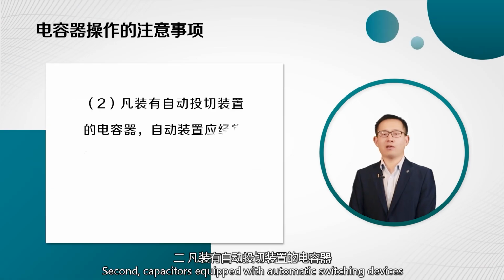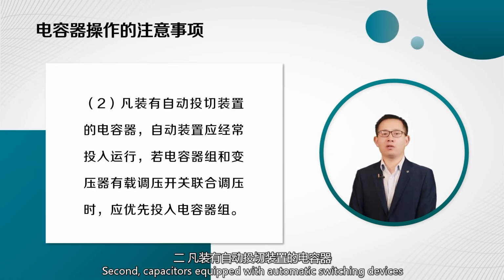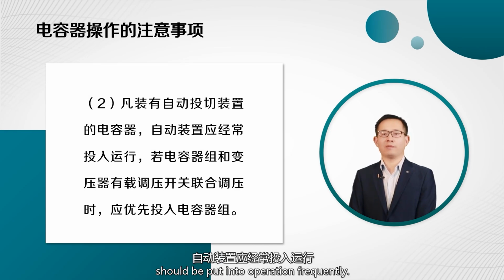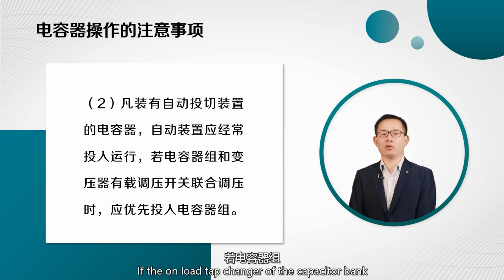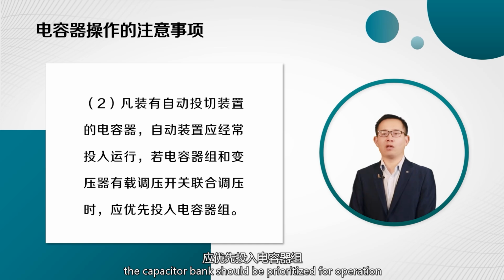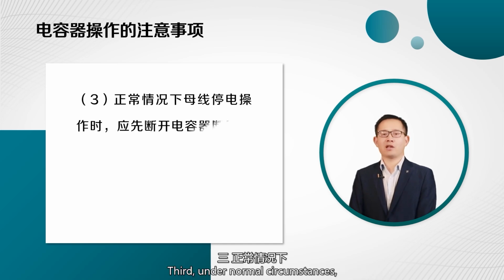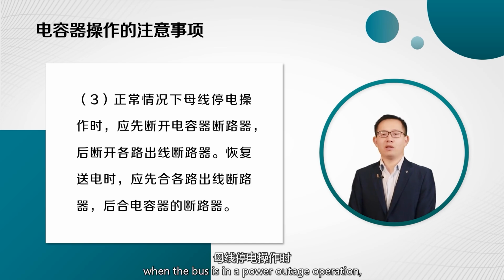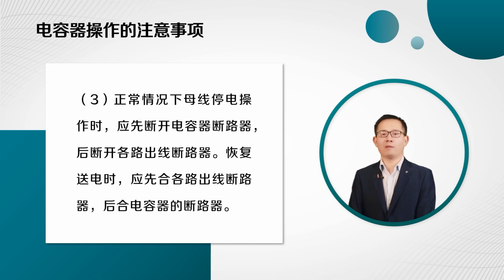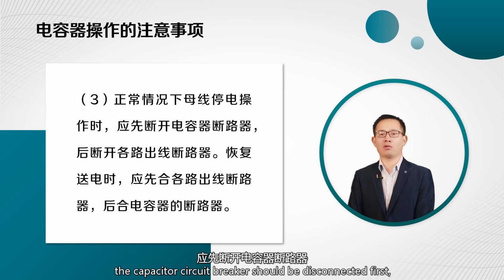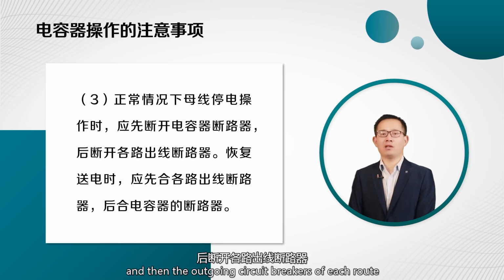Second, capacitors equipped with automatic switching devices should be put into operation frequently. If the on-load tap changer of the capacitor bank and transformer is used for joint voltage regulation, the capacitor bank should be prioritized for operation. Third, under normal circumstances, when the bus is in a power outage operation, the capacitor circuit breaker should be disconnected first, and then the outgoing circuit breakers of each route should be disconnected.